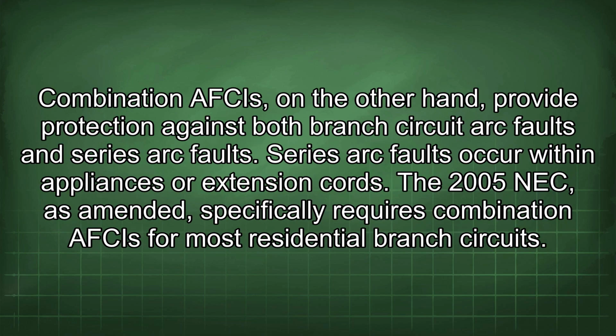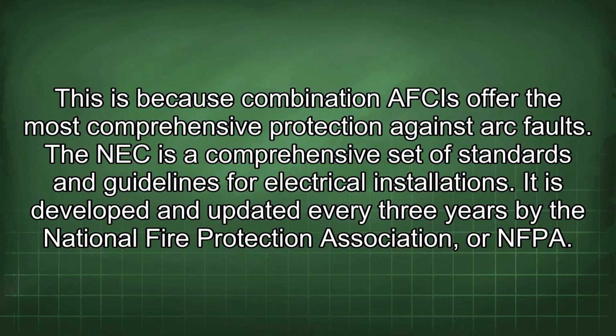Combination AFCIs, on the other hand, provide protection against both branch circuit arc faults and series arc faults. Series arc faults occur within appliances or extension cords. The 2005 NEC, as amended, specifically requires combination AFCIs for most residential branch circuits. This is because combination AFCIs offer the most comprehensive protection against arc faults.